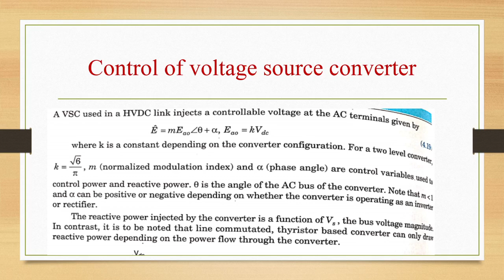Reactive power injected by the converter is a function of Vs, the bus voltage magnitude. In contrast, it is to be noted that a line commutated thyristor based converter can only draw reactive power depending upon the power flow through the converter.